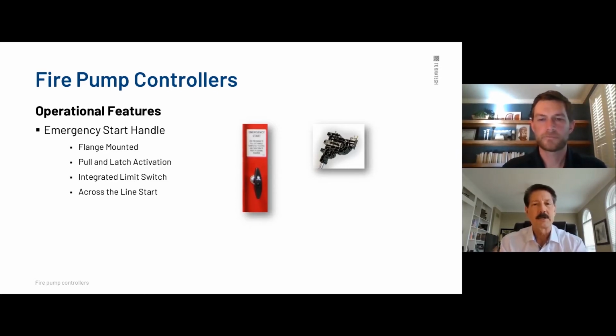Before you use the emergency start handle, we advise you to turn the flange mounted power handle off. Then pull your emergency start handle and lock it, and then re-engage and turn your flange mounted operator back on, putting power back to the controller itself. In doing so, it eliminates what Cole had just mentioned. When you're doing a start like this, you're going to end up doing it across the line. It doesn't matter if you have a reduced voltage controller or not, it's across the line. You could have a big motor there. It's going to draw a lot of inrush, at least 6 times full load amperage.